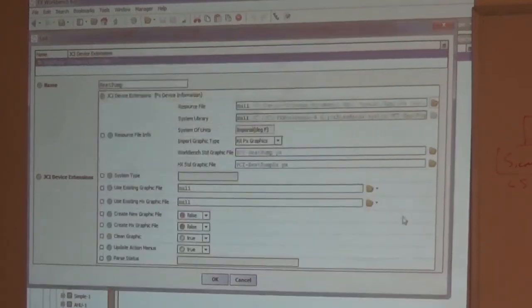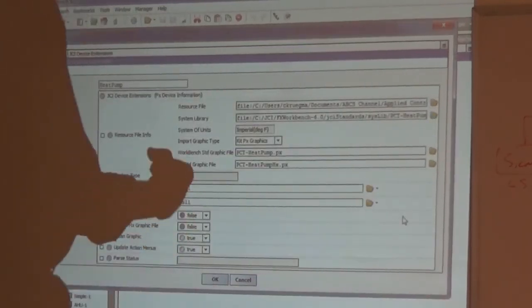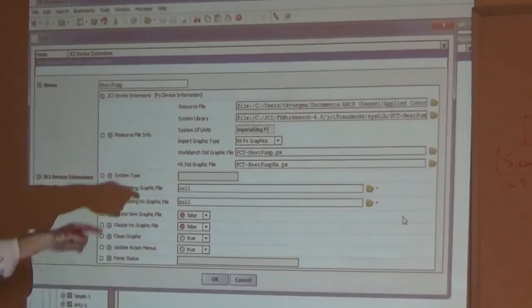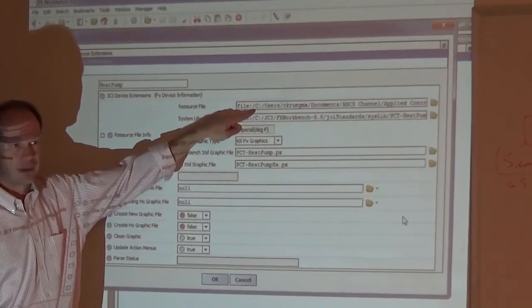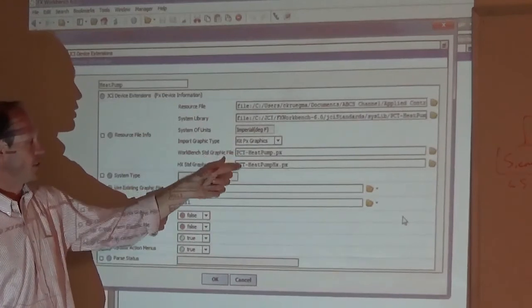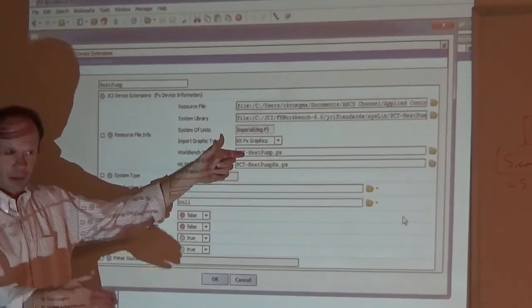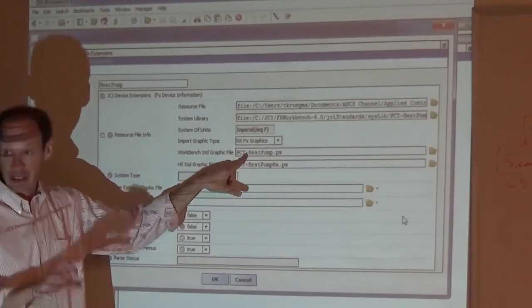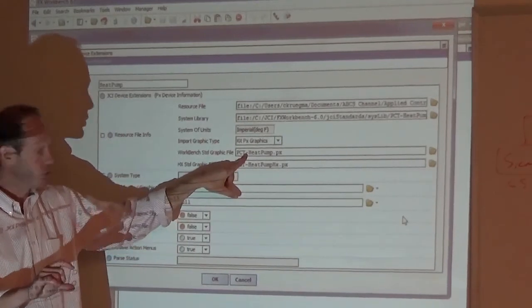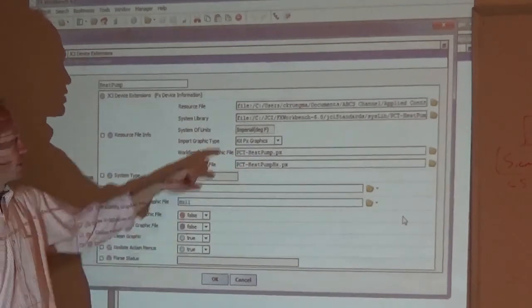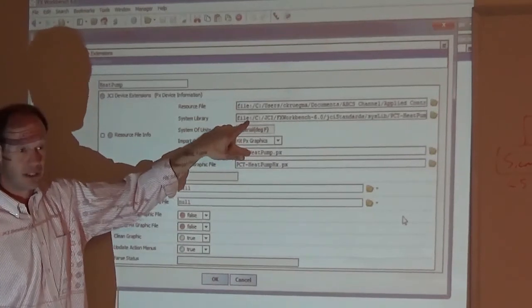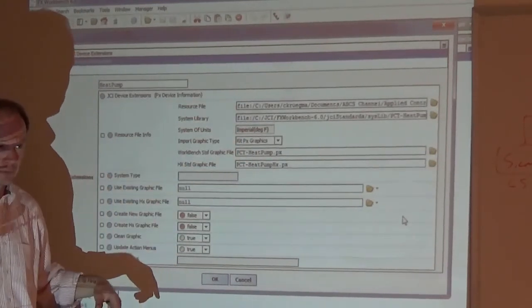I'll hit open, and that's what the spreadsheet is doing for you behind the scenes, it's picking, oh guess what, you have a heat pump application. I'm going to select the standard graphic file from those templates for heat pump, and that's the template that we have in the graphics, in the files folder, right? I'm picking those guys, and so it's also knowing how to bring in a certain subset of points for the heat pump because we configured it that way.